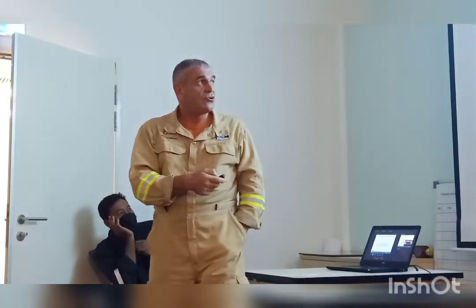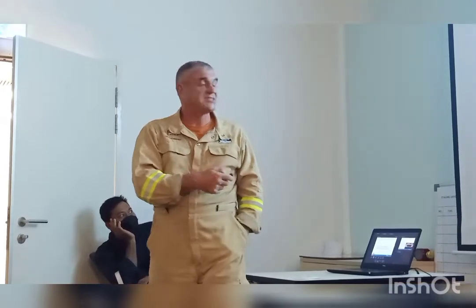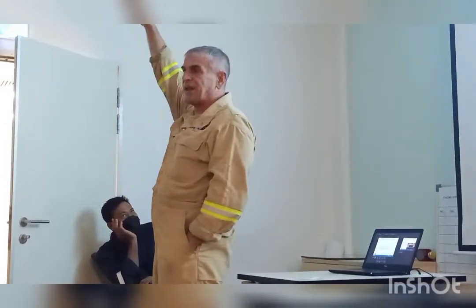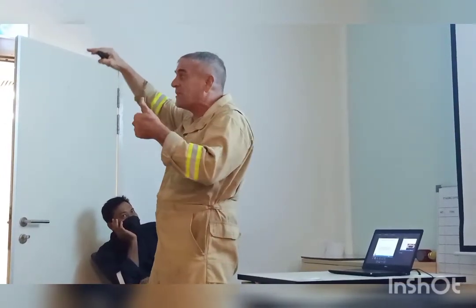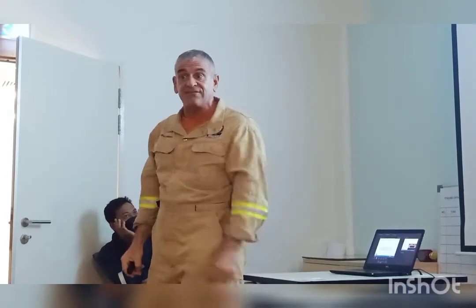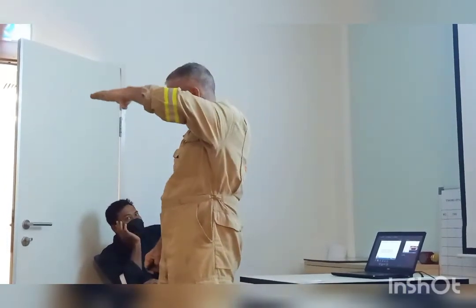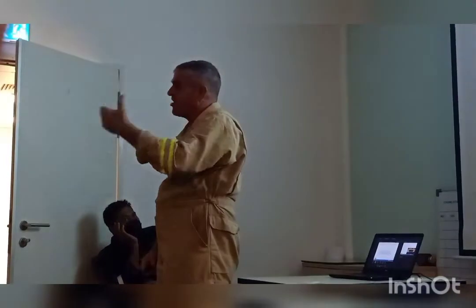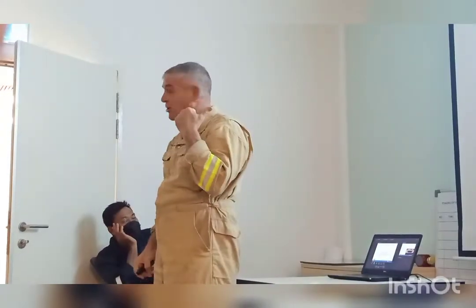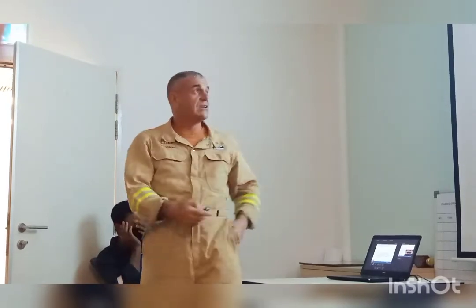But if we are quite high up there, and we know it's going to take about 1 hour per meter, that's probably giving us a good safety factor before that heat wave sinks. That gives us a time of how long we've got before we get boil over with that tank. And this is actually important when we look at the tank level.